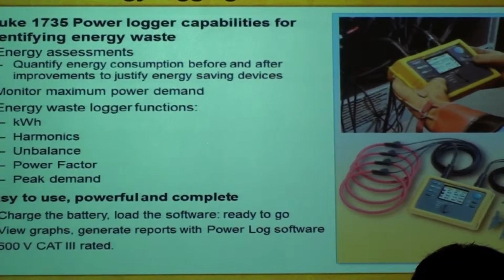No? Okay, so what is a category? If you look at an installation, okay, this hotel for instance, if I go to the basement, I will find the main incoming, right? Where the power is coming in. Cables are coming into the main panel. That area, which is what we call the service entrance, is the category 4 area. That is the area where if you have a fault, the energy produced is the worst. It's very high. It can cause this whole building to catch fire, or in fact, you'll have loss of life, okay?